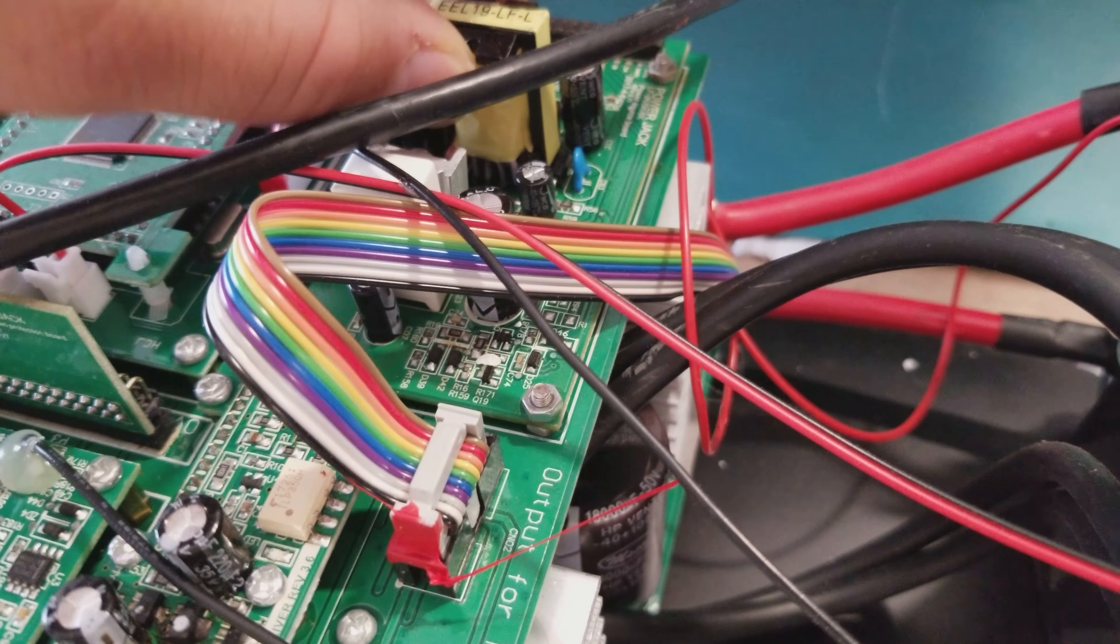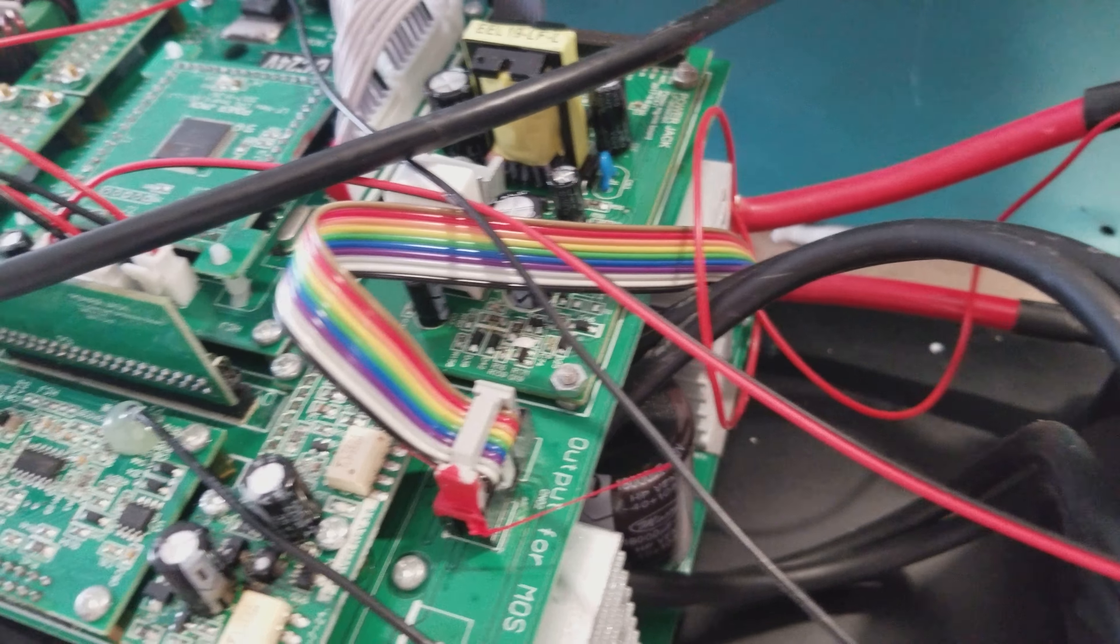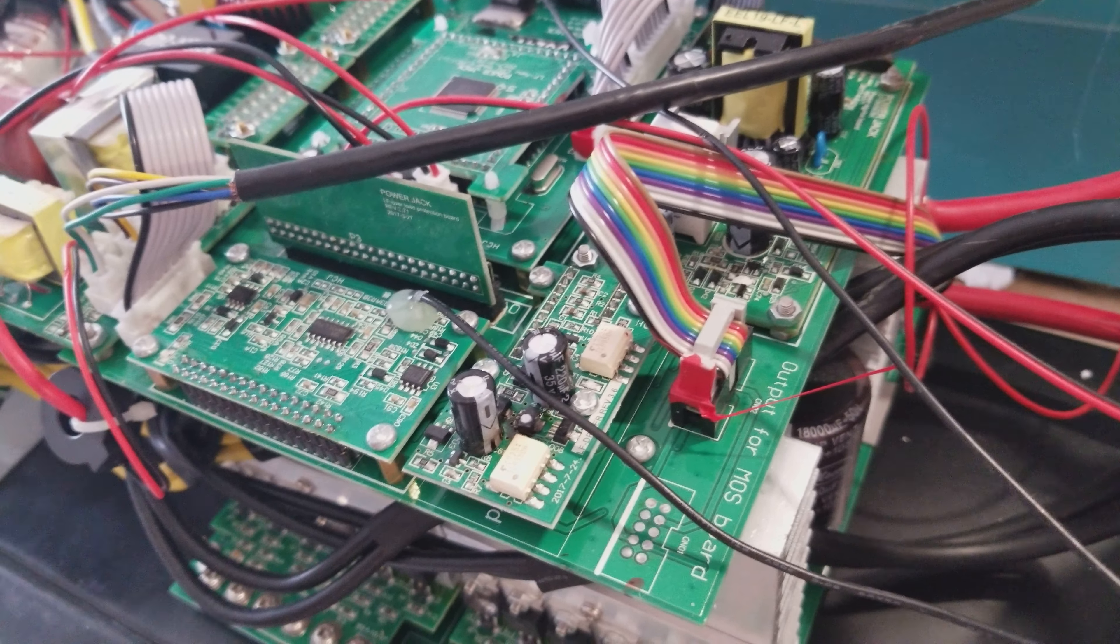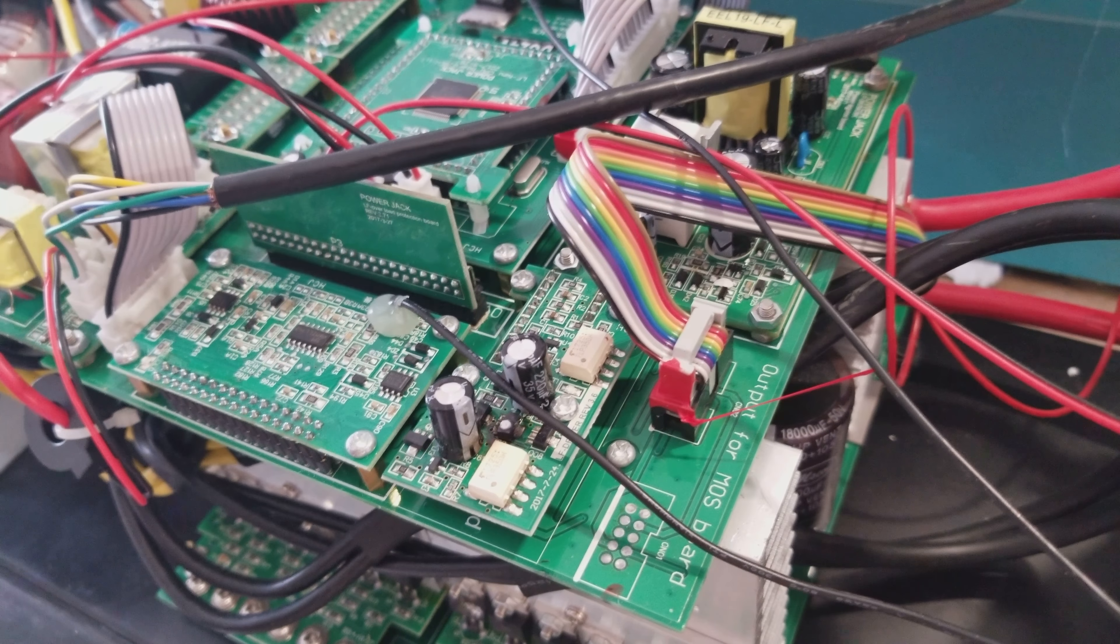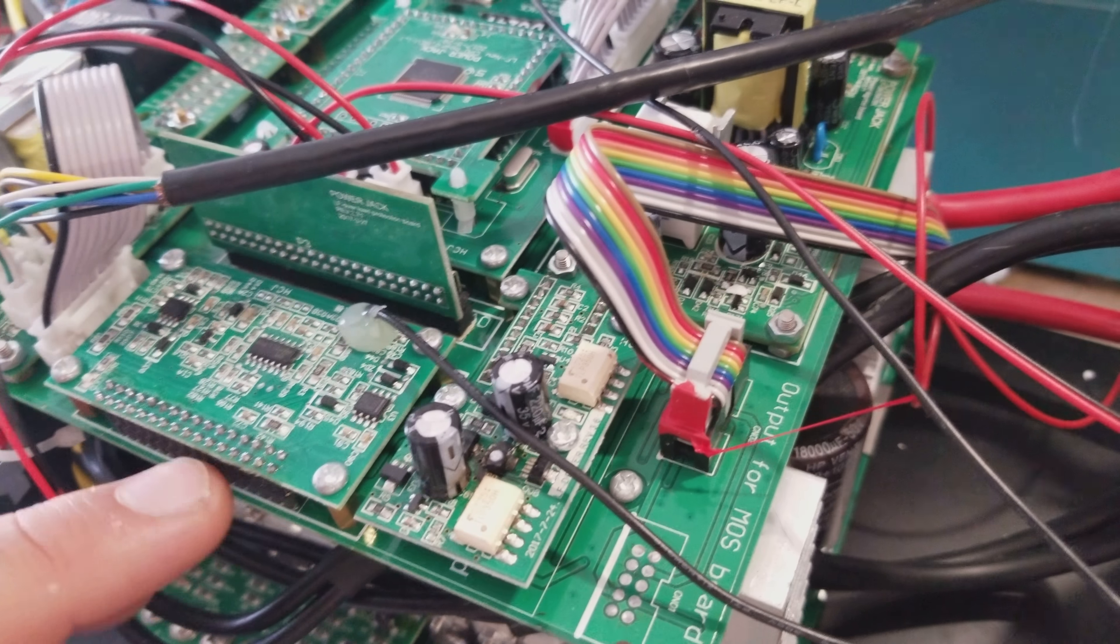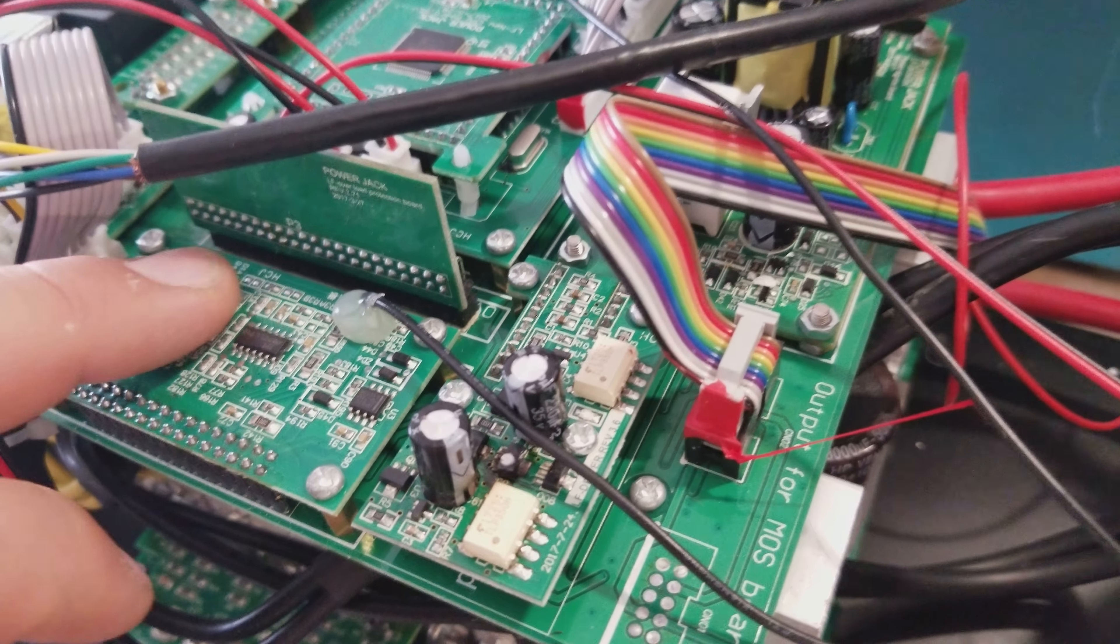say pulling out the power source board and then sticking it in another inverter and it's bad. And then it burns up that inverter. It's not worth the risk because you don't know if anything else has been damaged, especially with that kind of surge. And you may not even see it on there.